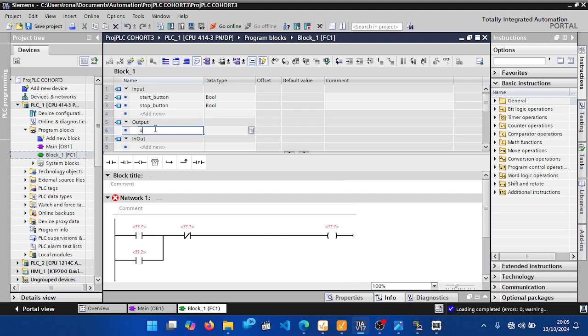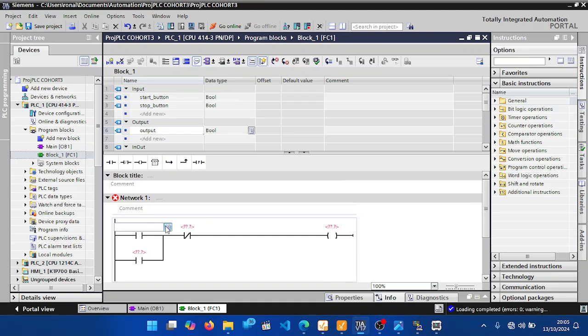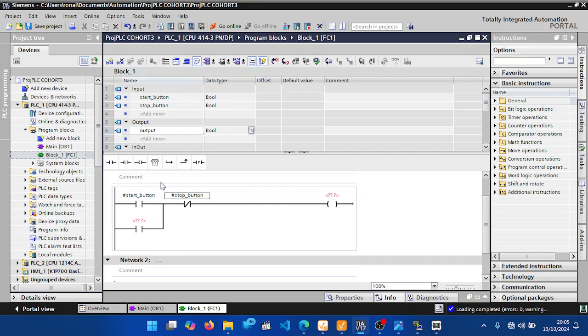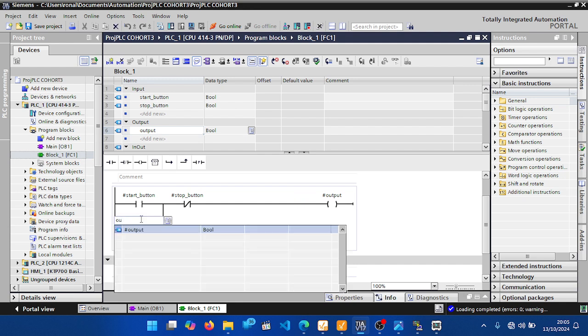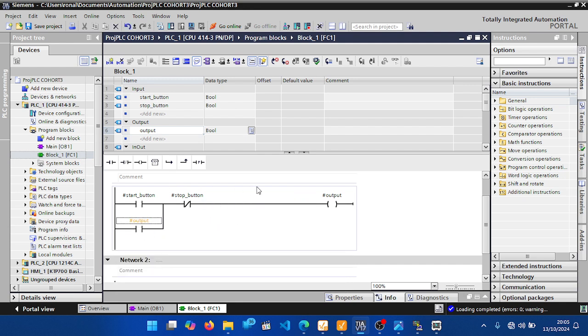At the output section, add an output variable of type Boolean. Assign the start button and stop button contacts to their variables. Notice there is no tag address — confirming these are temporary variables. Assign the output coil to the output variable. The subroutine is now done.